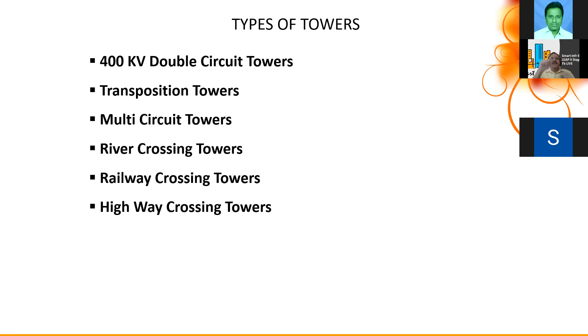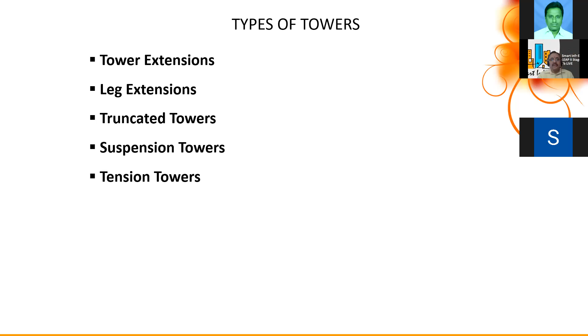Regarding tower extensions - transmission towers are standardized, though a line may run 300 kilometers with 700 towers, for example, in one line. But we don't design all 700 towers separately; we design 4 or 5 types of towers and provide for variations in height through extensions - tower body extension and leg extension. Leg extensions are used in hilly terrains, and body extensions are used for variation in height. For example, if I have a 40-meter tower, I may have body extensions up to 12 meters, making it 52 meters. Leg extensions added to that can range from 1.5 meters to 9 meters. So these are all the things to be known and noted here.